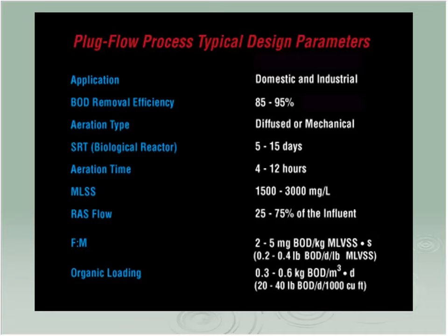We will vary this during the year. In the summertime, when our wastewater is coming in at about 70, 75 degrees, it's warmer, the bugs are more active. We don't need as many bugs to do the job. But as we approach October and the temperatures are starting to drop, for every 10 degrees Celsius drop in temperature on your input, and that pretty much goes from in August down to February, you're going to halve the activity of the organism. So if I'm going into wintertime and I'm afraid I'm going to halve the activity, I need more bugs to get the job done. So we'll tend to back off on our wasting and build up that population to get through the winter months. Then come March, we get them out of there because they're going to start going crazy.